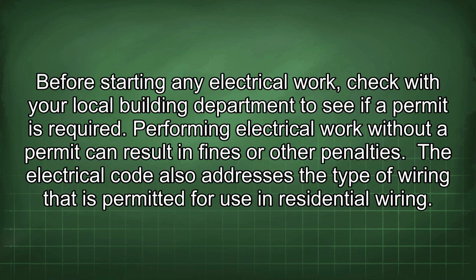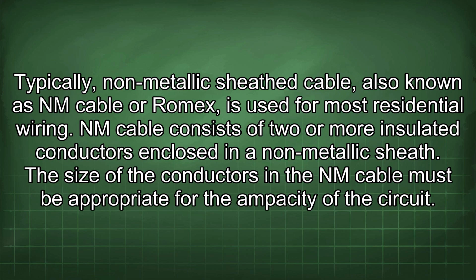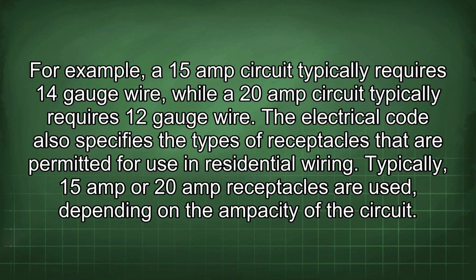The electrical code also addresses the type of wiring that is permitted for use in residential wiring. Typically, non-metallic sheath cable, also known as NM cable or Romex, is used for most residential wiring. An NM cable consists of 2 or more insulated conductors enclosed in a non-metallic sheath. The size of the conductors in the NM cable must be appropriate for the ampacity of the circuit. For example, a 15 amp circuit typically requires 14 gauge wire, while a 20 amp circuit typically requires 12 gauge wire.